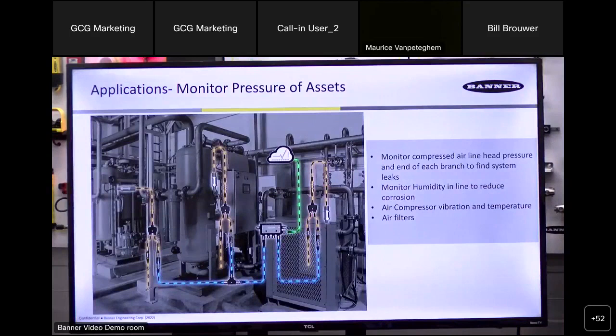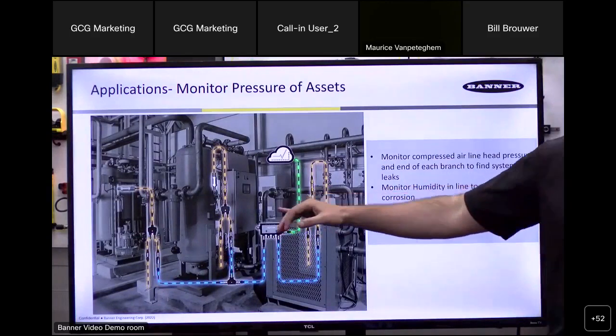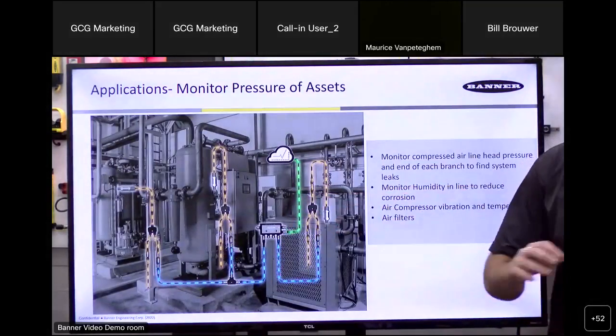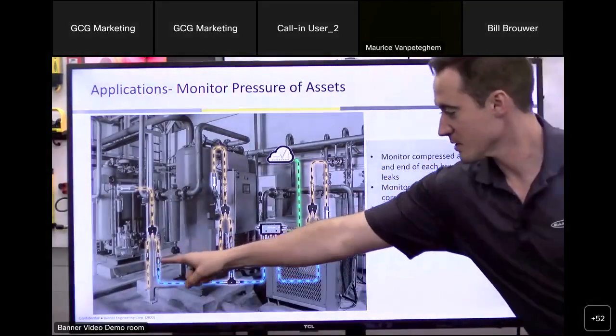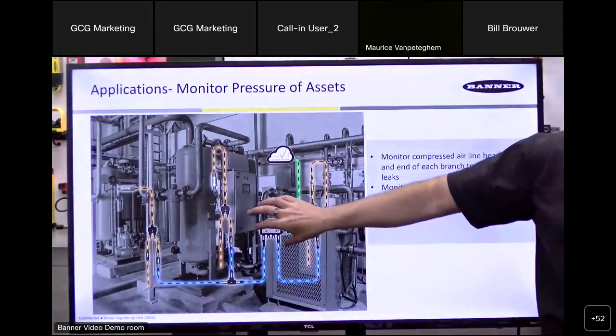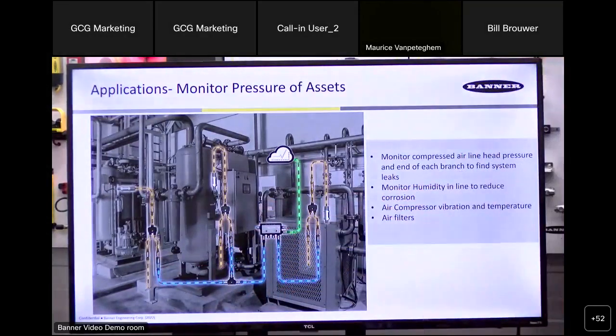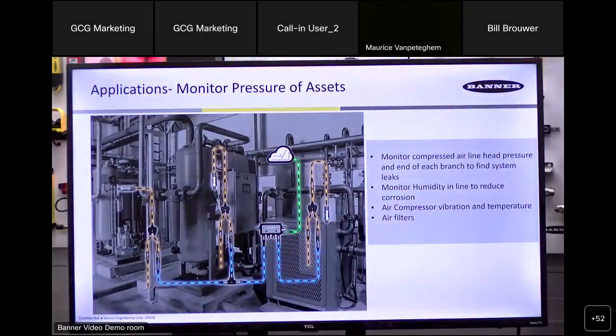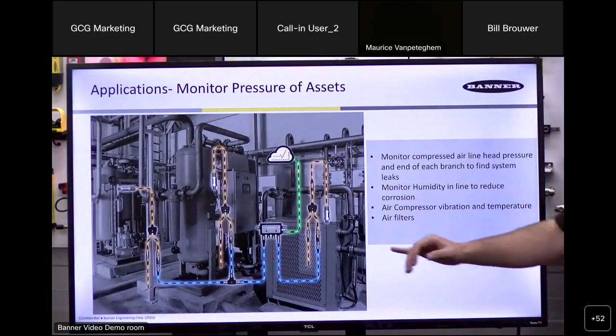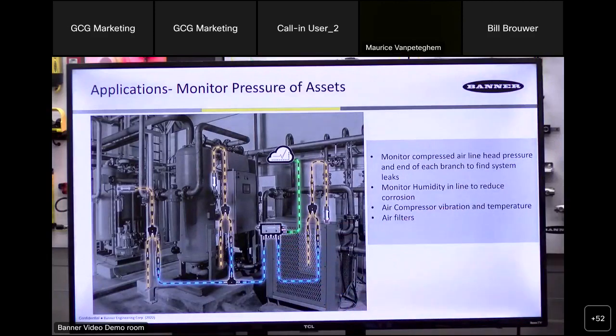Pressure monitoring is a big one in many applications. Like I said before, we were able to take that 4 to 20 milliamp or 0 to 10 volt signal from these devices, whether they're Banner devices or other manufacturers' devices, convert it over to a unified serial protocol, and capture that data before sending it to the DXMR90. So think things like air compressors, air filters, and maybe you want to mix and match and add more sensors to this type of application.